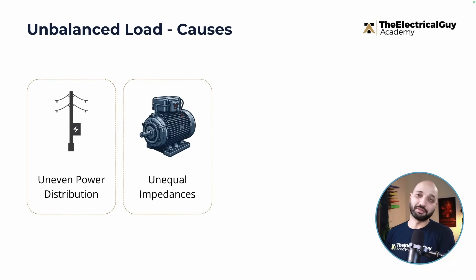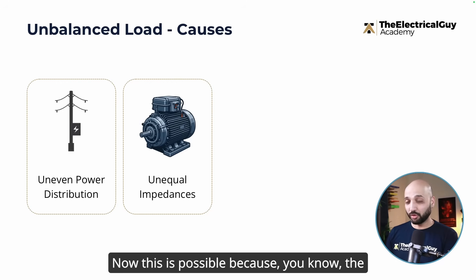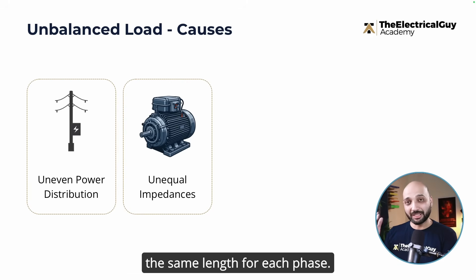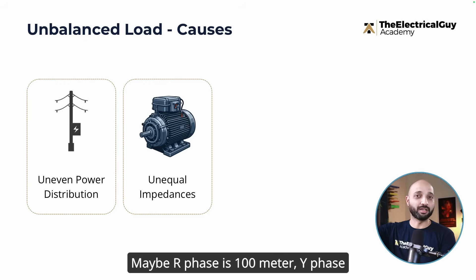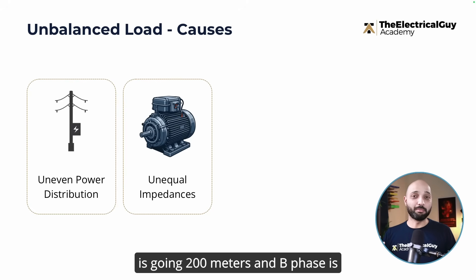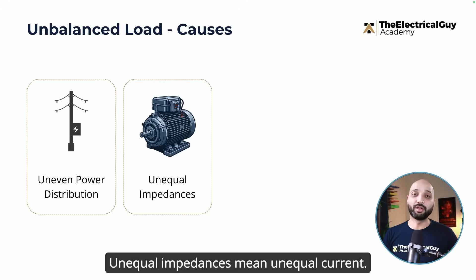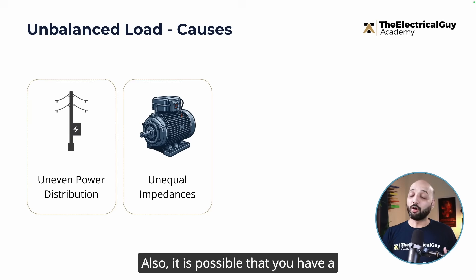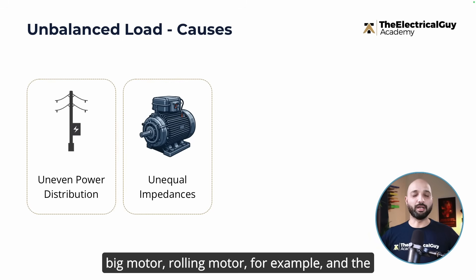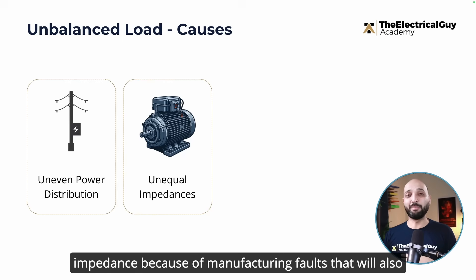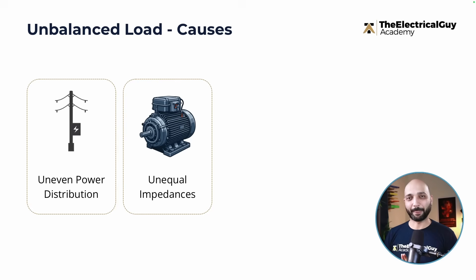The second cause is unequal impedances. Distribution cables are not necessarily the same length for each phase — maybe the R phase runs 100 metres, the Y phase 200 metres, and the B phase only 50 metres, so we have no control over that. It is also possible that a large rolling motor has three windings with different impedances due to manufacturing faults. Unequal impedances mean unequal current and then a lot of problems follow.